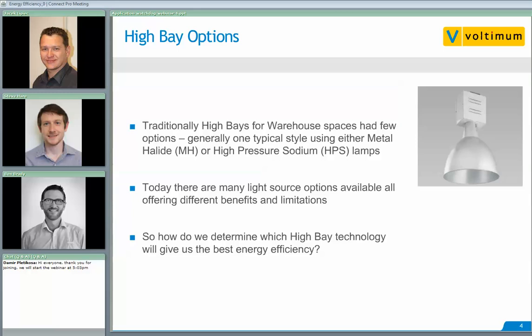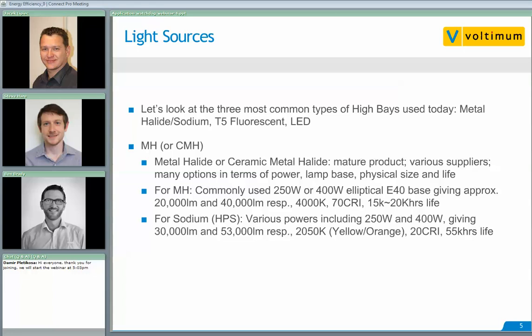How do we determine the high bay technology that will give us the best energy efficiency? Let's look at the three most common types used in high bays today: metal halide or sodium, T5 fluorescent, and LED. With regards to metal halide, or ceramic metal halide, it's quite a mature product with various suppliers who've been around in the industry for a very long time. There are many options in terms of power, lamp base, physical size, and lifetime. For metal halide, we commonly use 250-watt or 400-watt elliptical E40 base lamps.